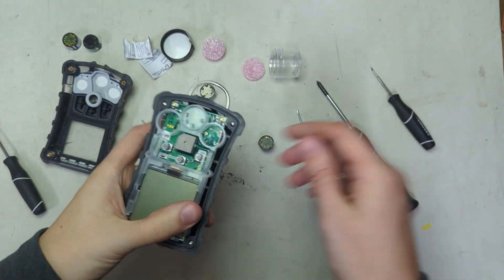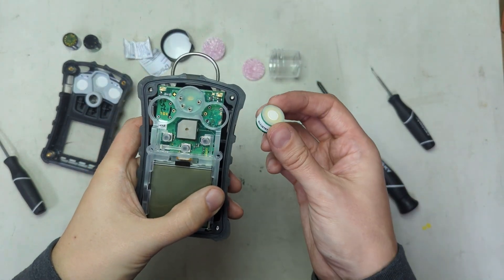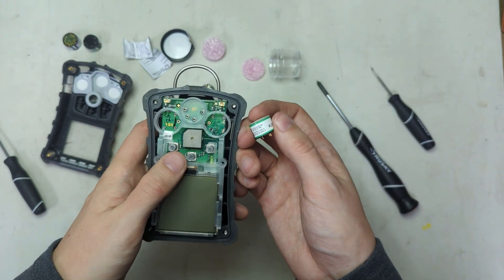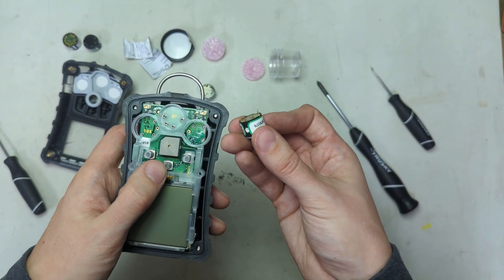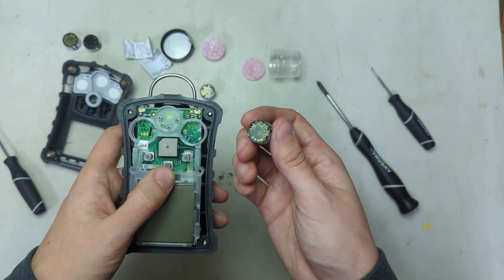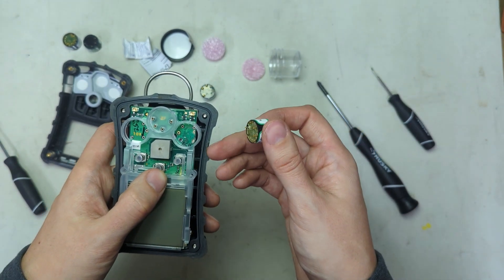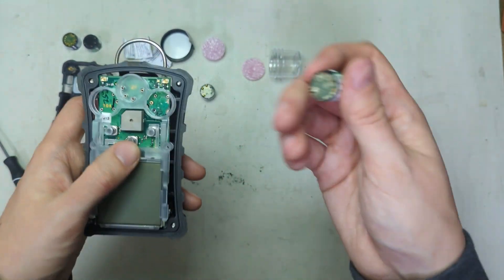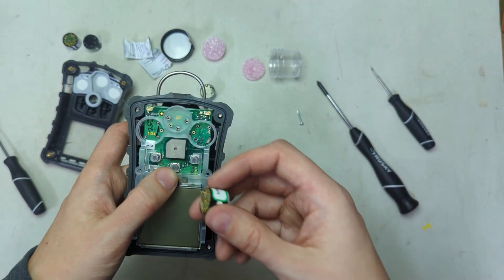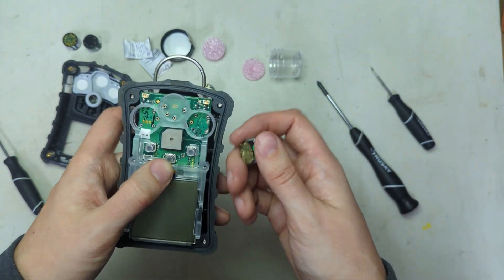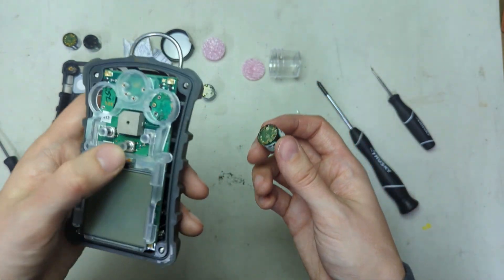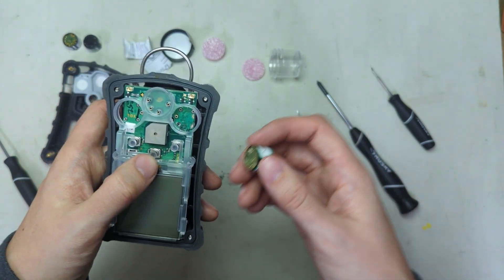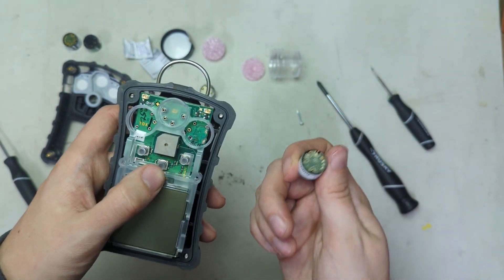You know, one thing I want to edit in here is, to avoid this type of damage, when your O2 sensor dies, get it out of there immediately, or send it into a repair shop immediately. You don't want to sit around and wait. It's another reason also that you should be calibrating these units once a month, just to check and make sure they're working properly, because the last thing you want is to go to do a job, you turn the unit on, the sensor's dead, you send it in, the board is now dead, now you're waiting on a new unit. So make sure you check these things out once a month, and make sure that if they have an O2 sensor, or any other sensor that dies, you get the sensor out of there immediately, or get the unit out the door.